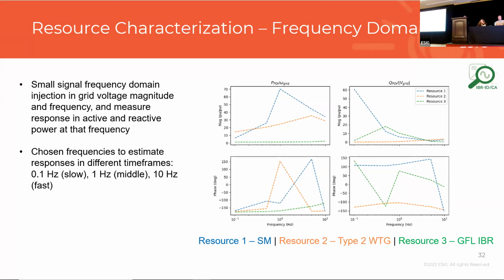The inverter, on the other hand, has no kind of reaction to the frequency changing. So the inverter is a resource in this particular configuration that, irrespective of how much the frequency changed on the network, whether it was a fast change or a slow change, essentially didn't respond. And that's captured in the transfer function. So the active power, delta P, is close to 0 for any change in frequency that occurs on the grid.